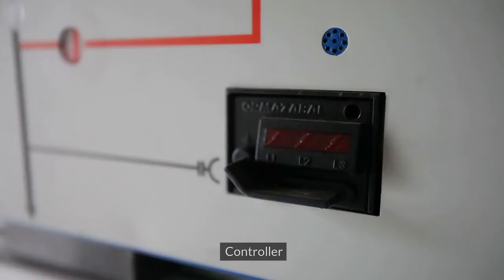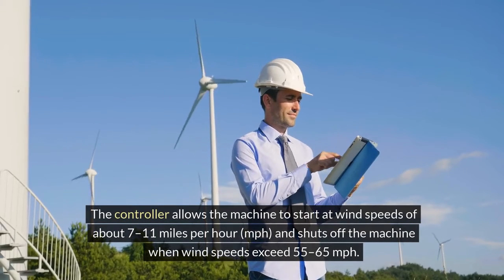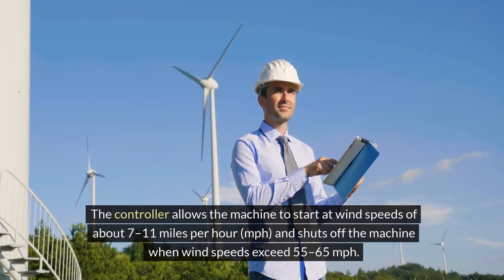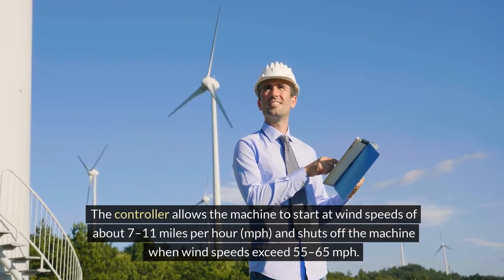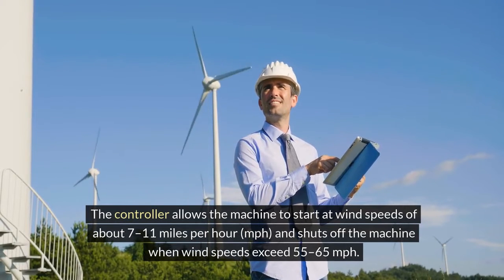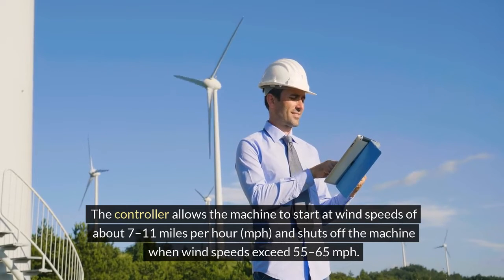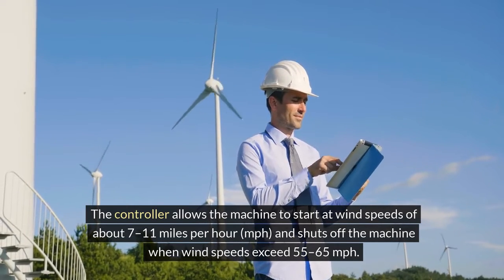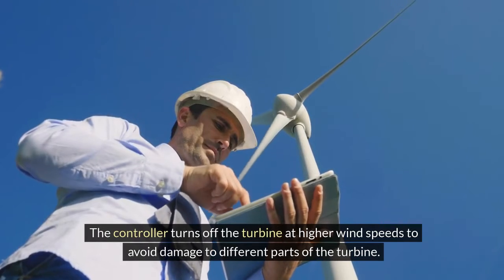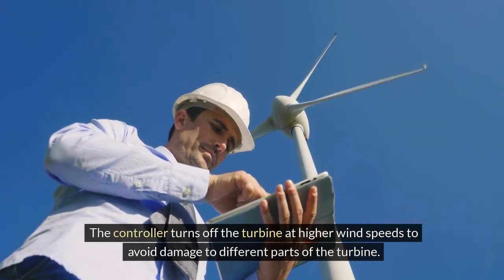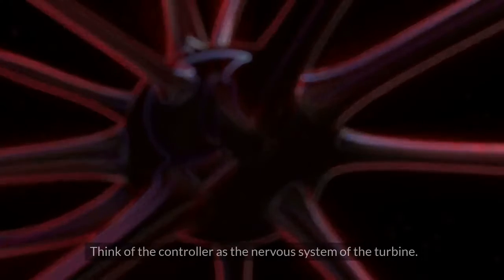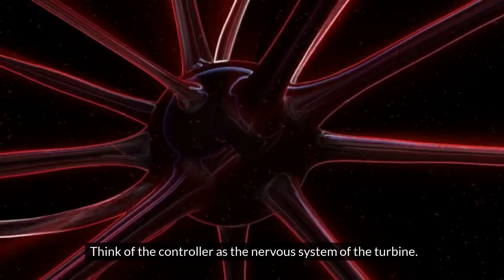Controller. The controller allows the machine to start at wind speeds of about 7 to 11 miles per hour, and shuts off the machine when wind speeds exceed 55 to 65 miles per hour. The controller turns off the turbine at higher wind speeds to avoid damage to different parts of the turbine. Think of the controller as the nervous system of the turbine.